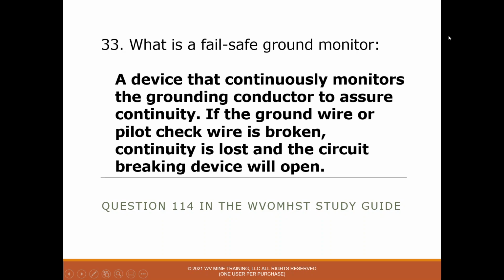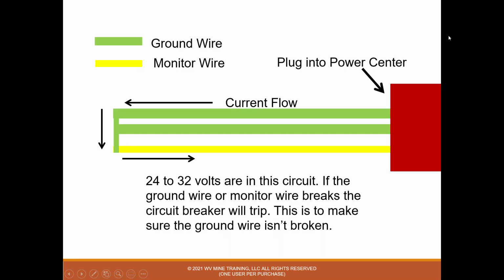33, what is a fail-safe ground monitor? And the answer is a device that continuously monitors the grounding conductors to assure continuity. If the ground wire or pilot check wire is broken, continuity is lost and the circuit breaking device will be open. So our very first question talked about a ground and how important it is to have that. So what we do is we actually monitor that ground.